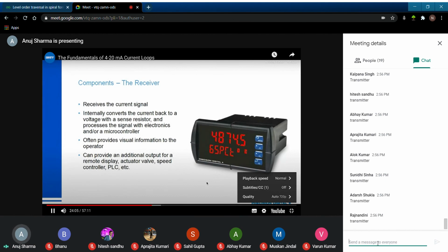Sometimes that's just displaying or recording the information. Other times you'll have additional outputs from these receivers, which could be relays for alarms, or serial communication signals to your control system, or even an additional 4 to 20 milliamp loop scaled differently going off to other devices. So the receiver can be any device on this loop, but they all have somewhat similar characteristics.